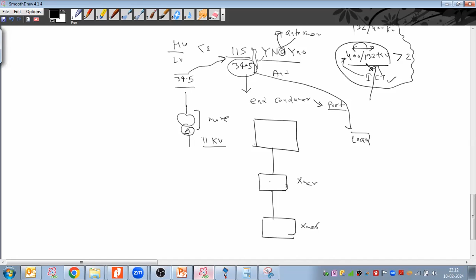I'm with you. What I'm telling you is that this is one good practice which I'm telling you. I'm telling you that in Asian countries we follow this kind of good practice for transformer type selection, but I have seen in countries like UK or US, in their grid they don't have this HV/LV ratio less than 2. They have 132 kV by 400 kV, or they go with 400 kV by 132 kV. In that case also, they are using the auto transformer, the ICT, they are using. So do not follow this statement of mine as, I mean, 100% do not follow this statement of mine.